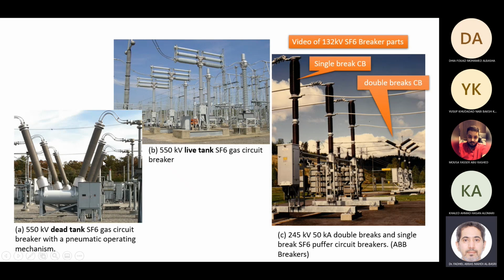To increase the breaking capacity for higher voltage, we sometimes use more than one breaker in series. This is one breaker in series with another breaker, so that they can be used for higher voltages. This is a live tank, where the chamber is at the same potential as the line voltage, while in a dead tank, the chamber in which the contacts are located is at ground potential. It's not that the contacts are grounded. It means this container in which the contacts are located is grounded. That's why they call it a dead tank.